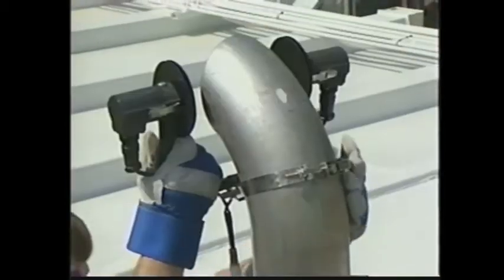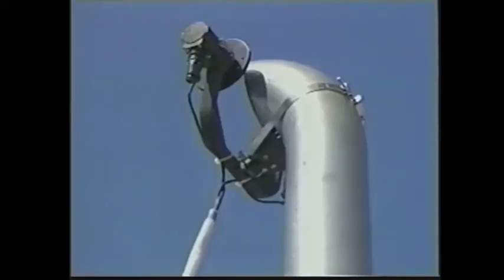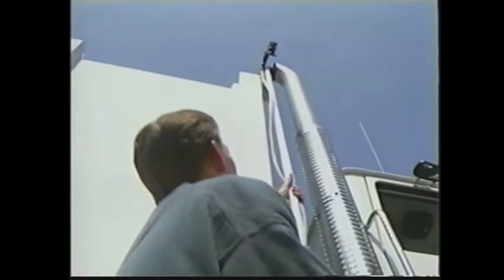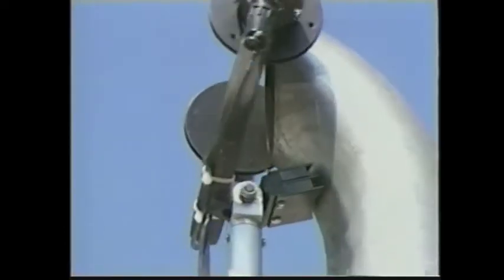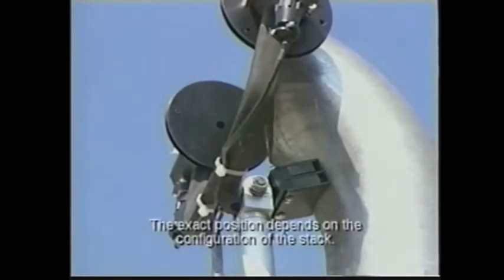Always use caution. Keep cables away from a hot stack. It can also be positioned from the ground with the extension pole. The exact position of the sensor head depends on the stack configuration.